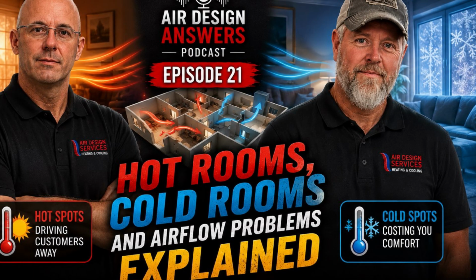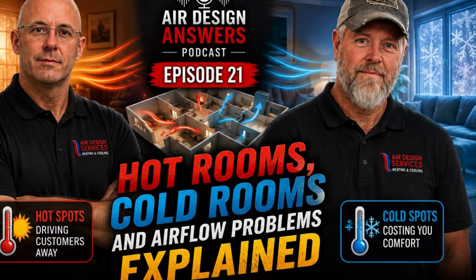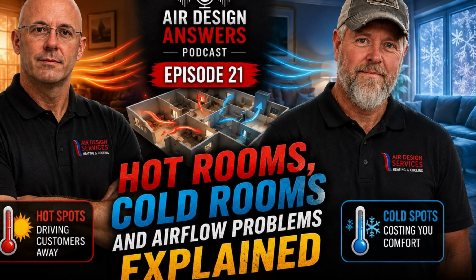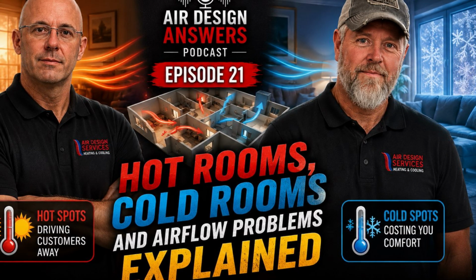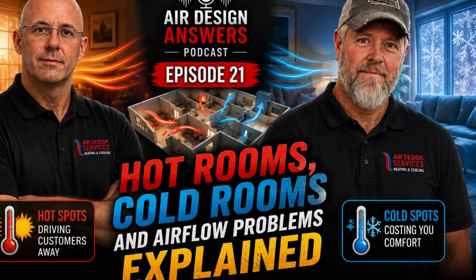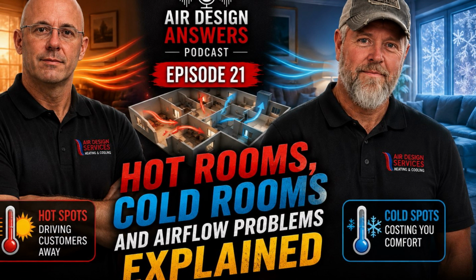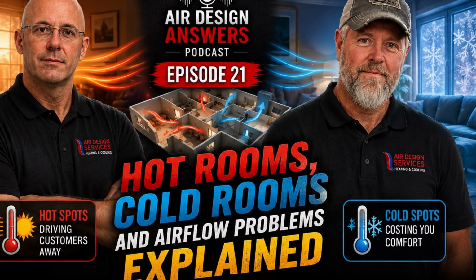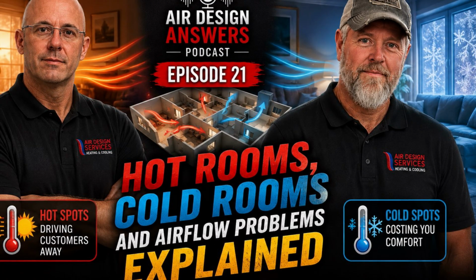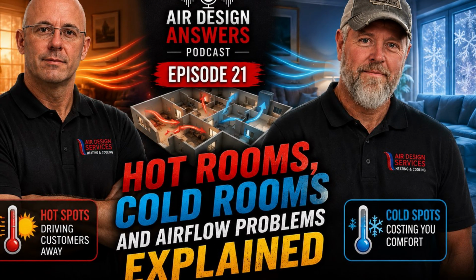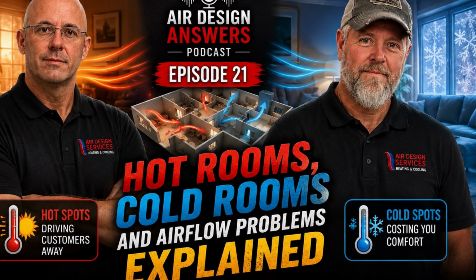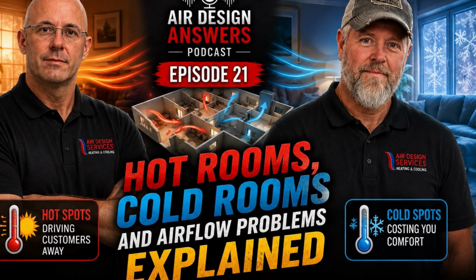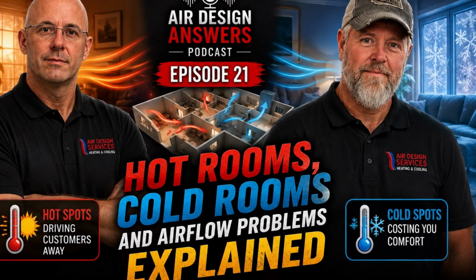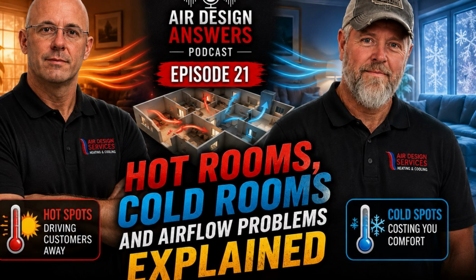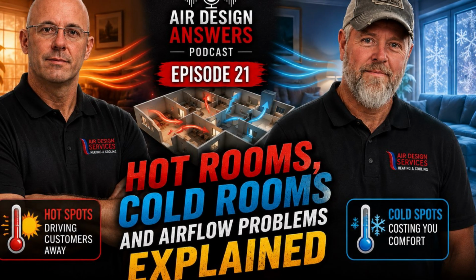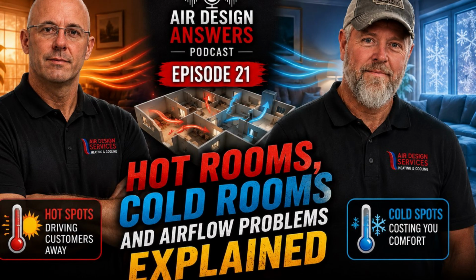Another thing homeowners should understand is that perfect temperature uniformity isn't realistic. That's an important point. No house maintains exactly the same temperature in every room all the time. There will always be slight differences. The goal is comfort, not perfection. Sometimes people expect every room to stay within a fraction of a degree. In reality, a couple degrees of variation throughout a home is very normal. Now, if you're dealing with 5, 6, 7, or 8 degree differences, that's when investigation becomes worthwhile. Especially if it's affecting sleep, productivity, or overall comfort.